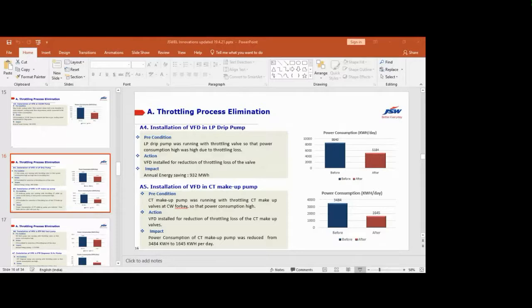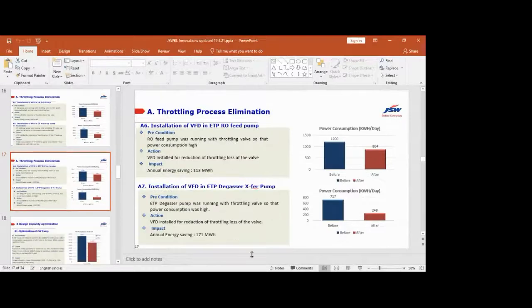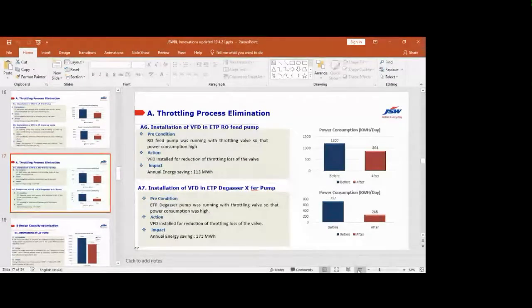And installation of VFD at the CT makeup pump. Same, we were getting throttling at the CT makeup pump. We provided the VFD, and the consumption went from 3484 kilowatt hour to 1645 kilowatt hour per day. Installation of VFD in the ETP RO feed pump. The RO feed pump was running with a throttling valve, so again a VFD was provided, and the same for the ETP Degasser transfer pump.